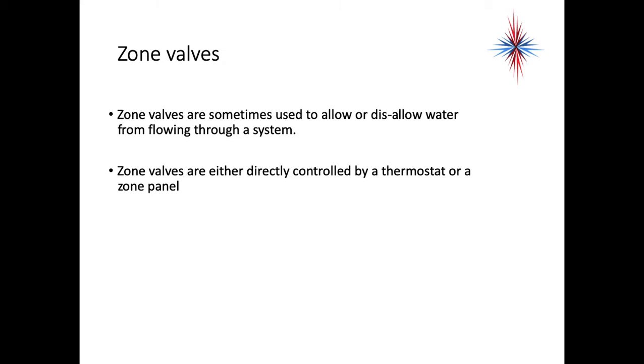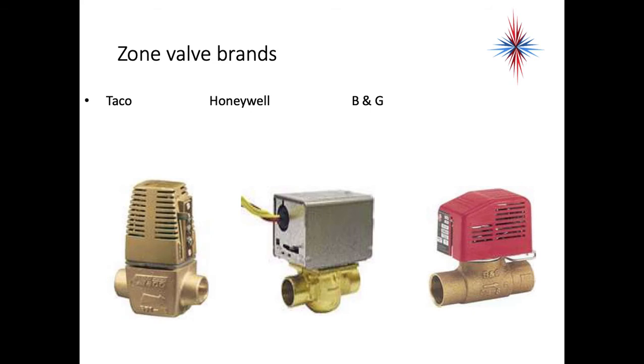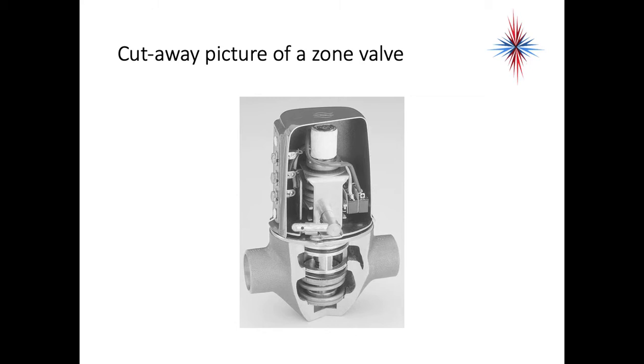Zone valves allow or disallow water from flowing through a system, controlled by a thermostat or zone panel. Brands include Taco, Honeywell, and B & G. When a thermostat calls for heat, the zone valve opens and allows the circulator to run water through the appropriate space. Inside, a heat motor pulls or pushes a plunger to allow water flow. When the set point is reached, the thermostat opens, de-energizing the heat motor, and a spring pushes the valve back closed.